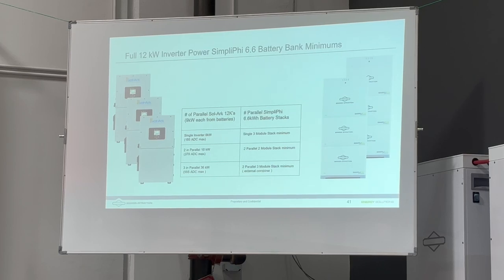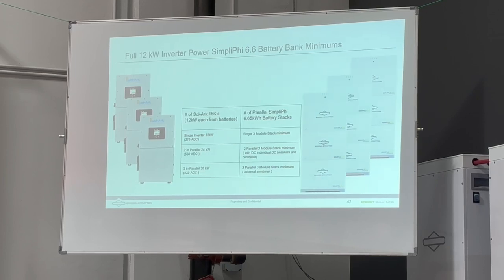So if I'm paralleling three Sol-Ark 12Ks, I'll be drawing a maximum of 9 kilowatts out of each 12K from batteries - that's 27 kilowatts total, so I'd need at least two of these battery stacks to provide that power. You want to size your batteries based on the power draw. Similarly, with three Sol-Ark 15Ks, basically a single stack is designed to provide the power for a 15K.